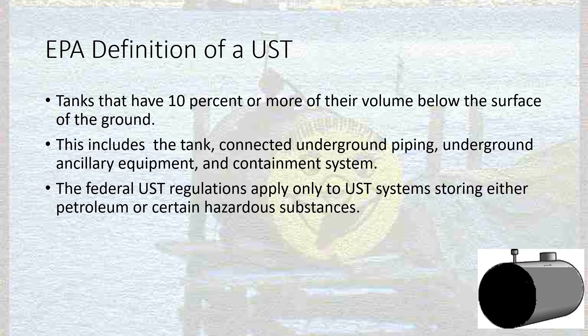The EPA definition of a UST is any tank that has 10% or more of its volume below the surface of the ground. This takes into consideration piping also, and includes the tanks, underground piping, underground equipment, and the containment systems associated with USTs. If more than 10% of the volume — including the piping — is underground, that makes it a UST. So if you have an abnormally long piping run, a tank that wouldn't normally be considered a UST now would be — though I've never seen that happen, it's theoretically possible.